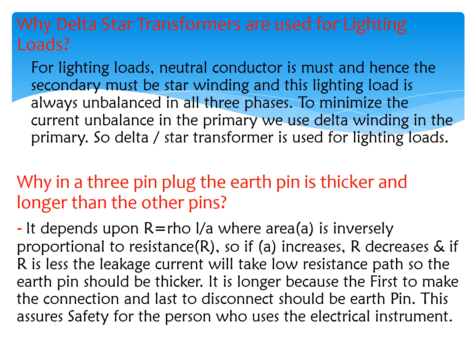So delta star transformer is used for the lighting loads, and also there is always a possibility of having ground faults in the lighting circuits. So when you are using a delta star transformer, even though there is a ground fault on the secondary side, it will not reflect to the primary as the primary winding is a delta winding.